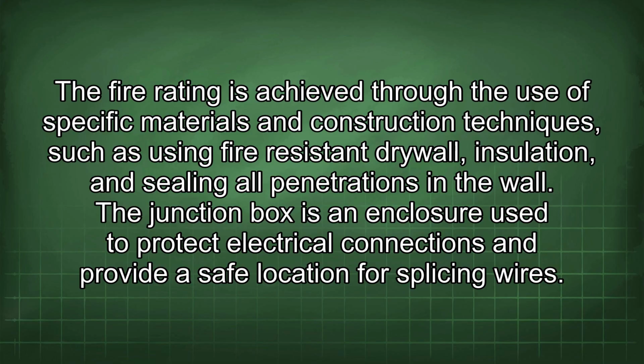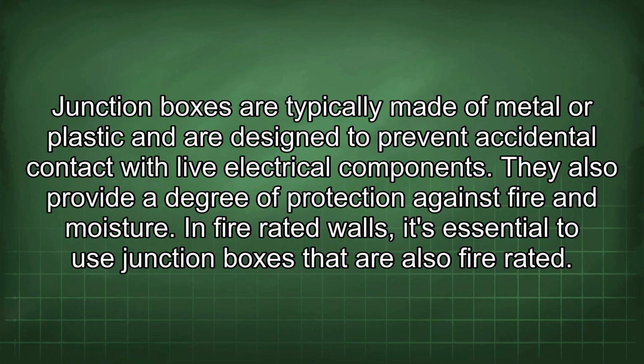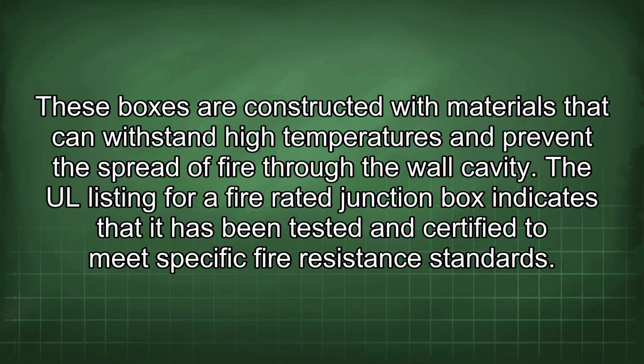The junction box is an enclosure used to protect electrical connections and provide a safe location for splicing wires. Junction boxes are typically made of metal or plastic and are designed to prevent accidental contact with live electrical components. They also provide a degree of protection against fire and moisture. In fire-rated walls, it's essential to use junction boxes that are also fire-rated. These boxes are constructed with materials that can withstand high temperatures and prevent the spread of fire through the wall cavity. The UL listing for a fire-rated junction box indicates that it has been tested and certified to meet specific fire resistance standards.